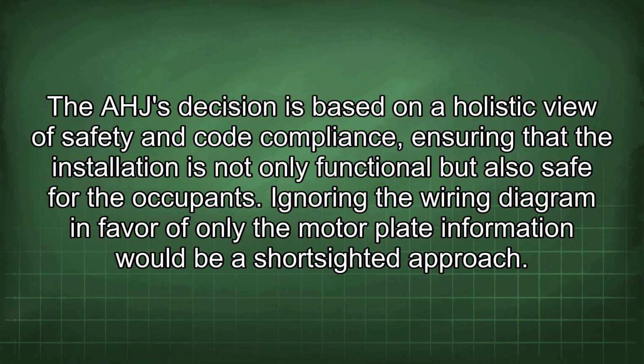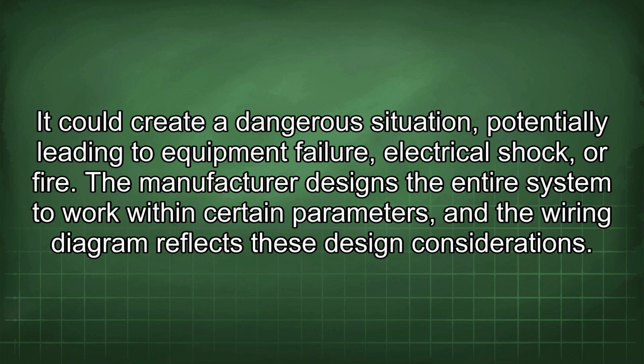The AHJ decision is based on a holistic view of safety and code compliance, ensuring that the installation is not only functional but also safe for the occupants. Ignoring the wiring diagram in favor of only the motor plate information would be a short-sighted approach. It could create a dangerous situation, potentially leading to equipment failure, electrical shock, or fire. The manufacturer designs the entire system to work within certain parameters, and the wiring diagram reflects these design considerations.